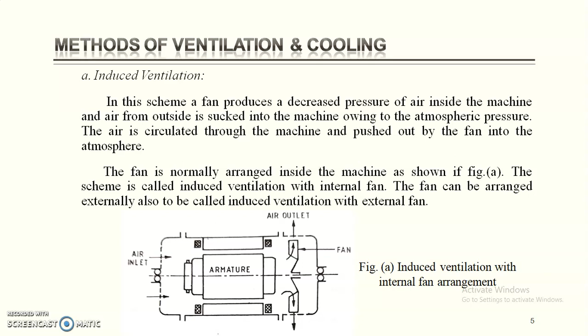As you can see, the figure shows the arrangement of induced ventilation, with the air inlet on the left hand side and the air outlet on the right hand side. Because of the rotation of the fan, it creates a low pressure inside the machine, so air is sucked in from the air inlet, owing to the atmospheric pressure on the air outlet. The fan is arranged internally, so it is called induced ventilation with internal fan. The fan can also be arranged externally, which is called induced ventilation with external fan.